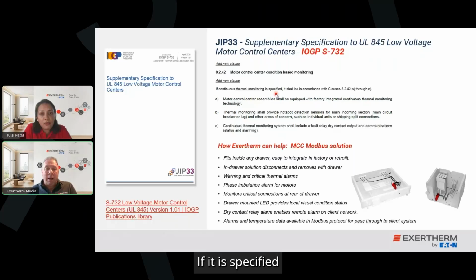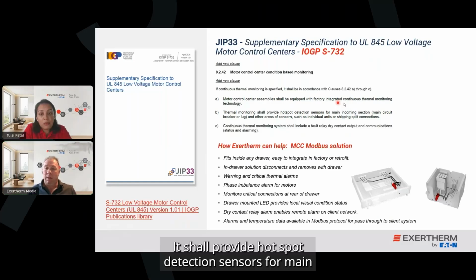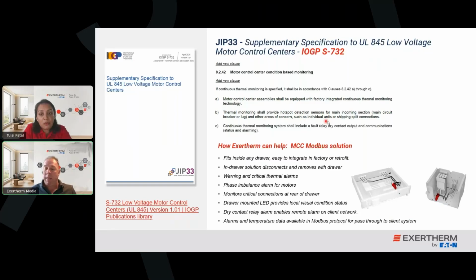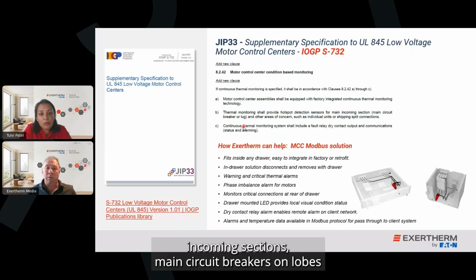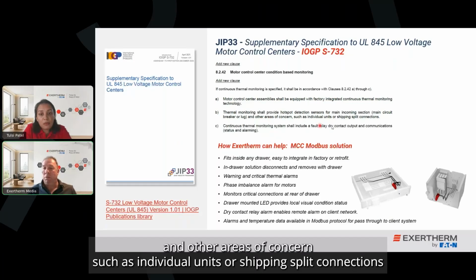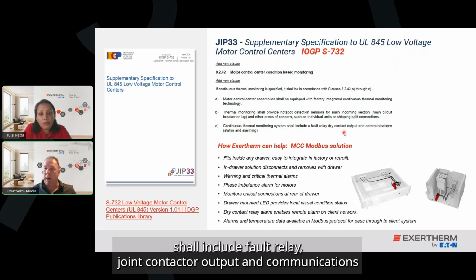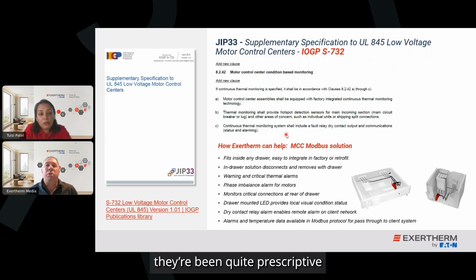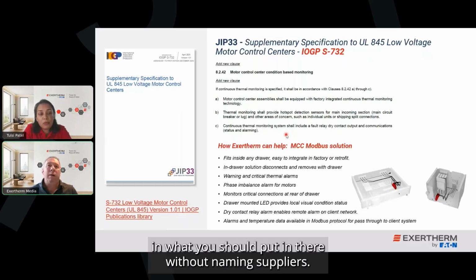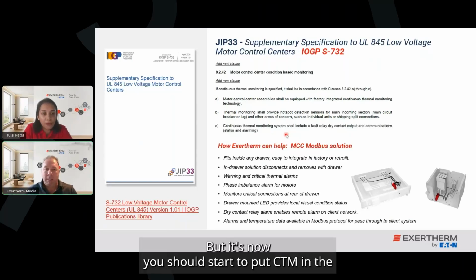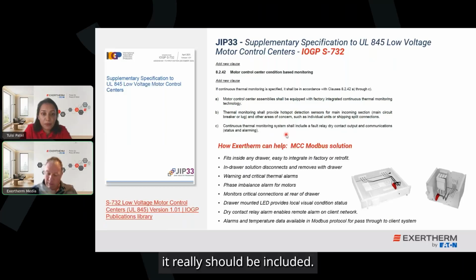continuous thermal monitoring, if it's specified, then it shall be in accordance with the 3 clauses below. Shall be equipped with a factory integrated CTM technology. It shall provide hotspot detection sensors for main incoming sections, main circuit breakers or lugs, and other areas of concern, such as individual units or shipping split connections. Shall include fault relay, dry contact output, and communications. So they've been quite prescriptive in what you should put in there without naming suppliers, but it's no, you should start to put CTM in there. It really should be included.